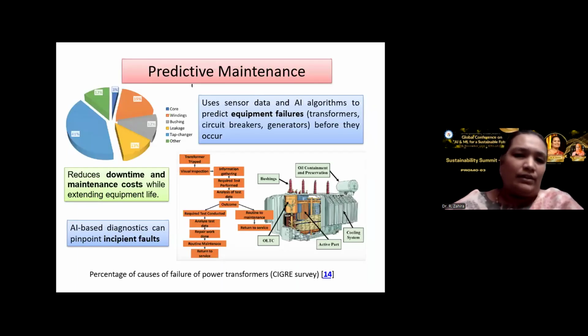For example, if I take a transformer, we have many parts for predictive maintenance - the core, winding, bushing, leakage, tap changing and others. Nearly 7 parameters in this transformer. If monitored properly, the life of the transformer will increase, proper maintenance can be done, and equipment failure can be identified at the pre-stage itself, so we can take it for maintenance and have proper fault identification.